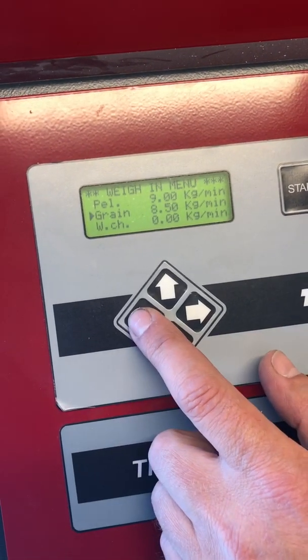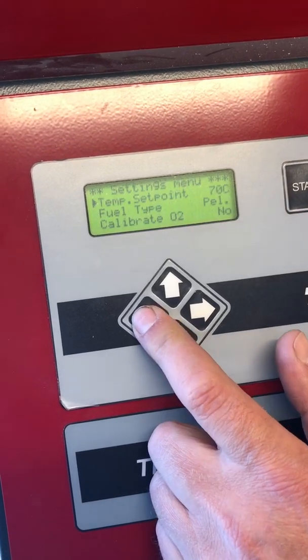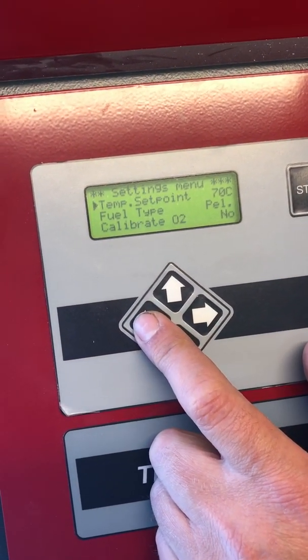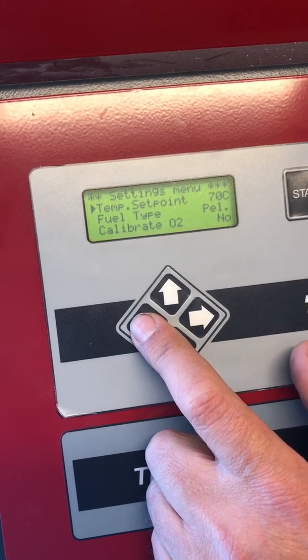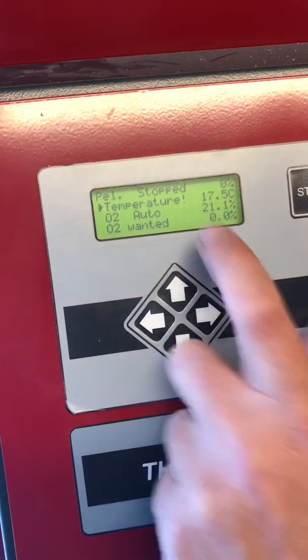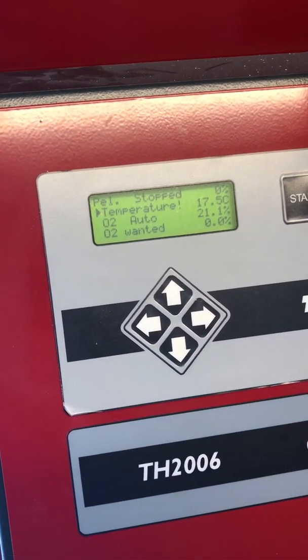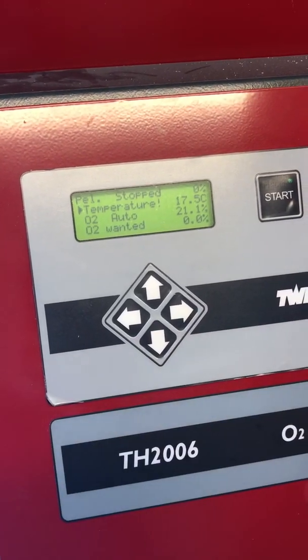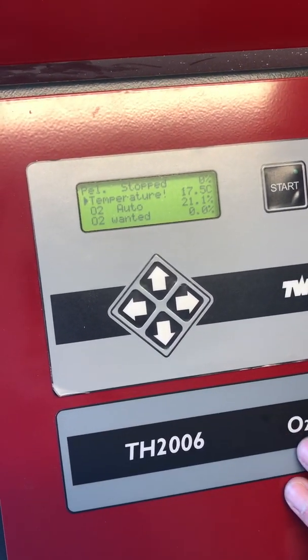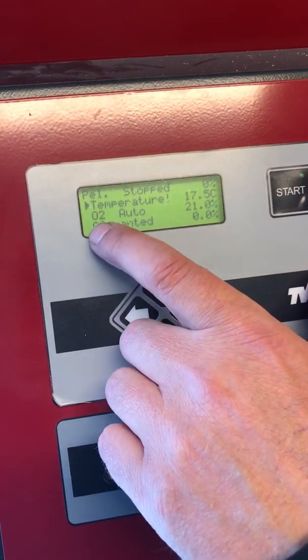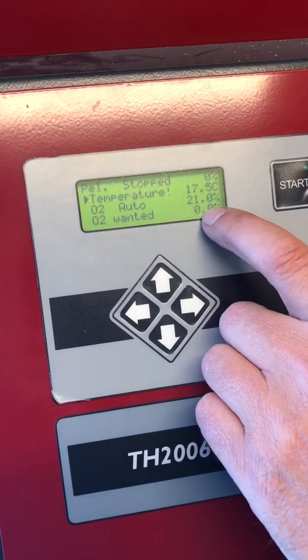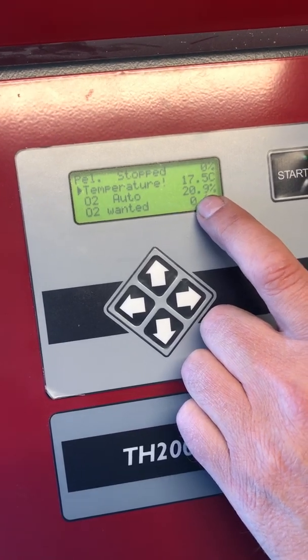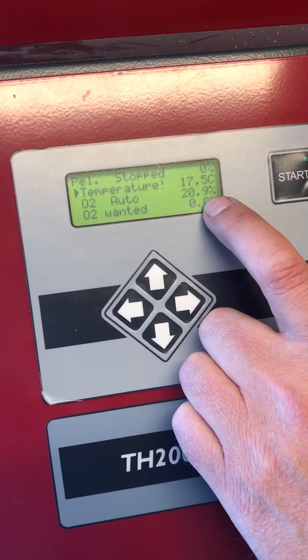So that means in the grain program we have a maximum and a minimum, and it finds out together with the lambda probe what amount of fuel it has to add. So now it's ready to start up. Before we do the startup, we'll check that the O2 auto — that's the lambda probe — in the fresh air around us shows 20.9% O2. This one is okay.